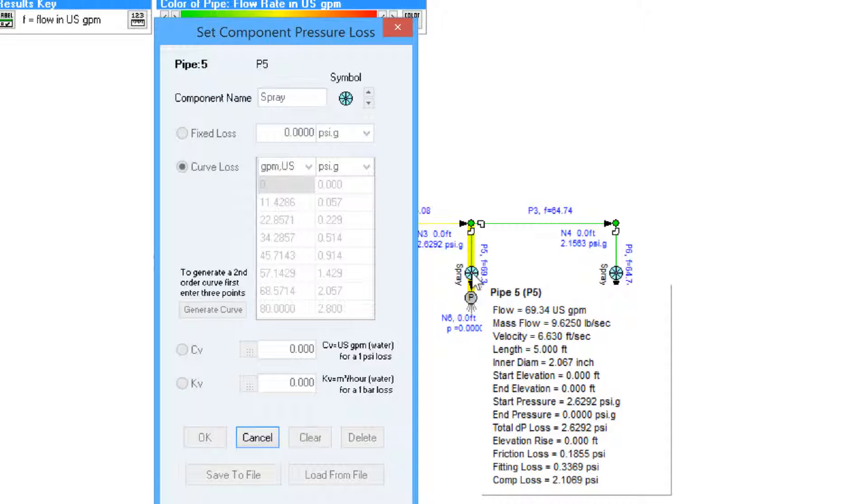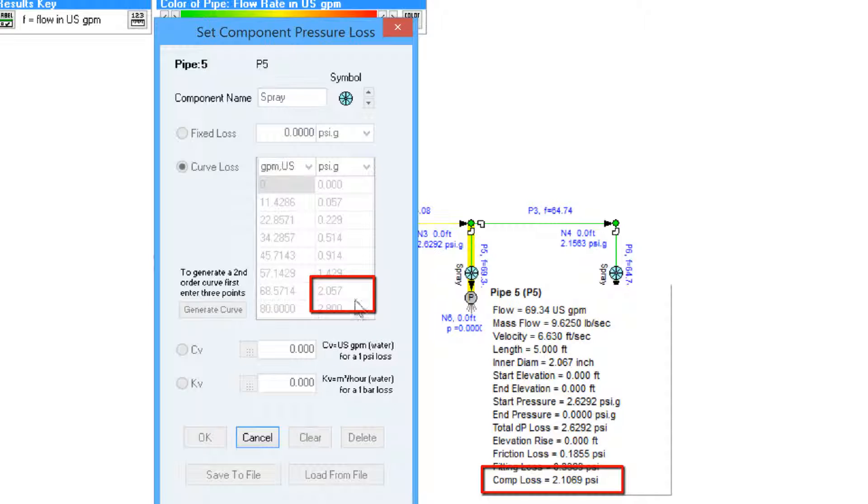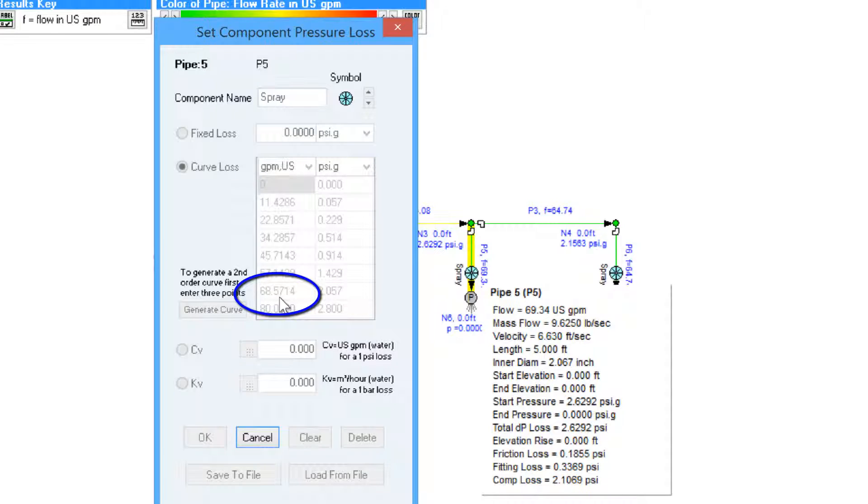we can compare the component loss for the calculated values with the curve loss data that is specified in the component screen. So in this case we can see the component loss is 2.1 psi which corresponds to a flow rate of just over 68.57 US gallons per minute and that also ties in with the flow rate that has been calculated.